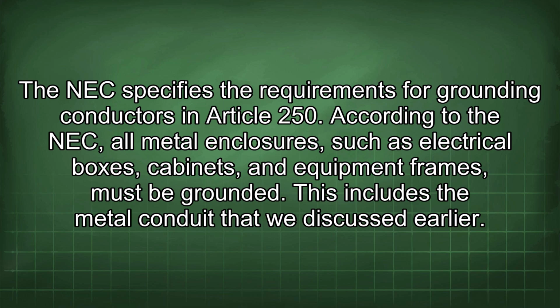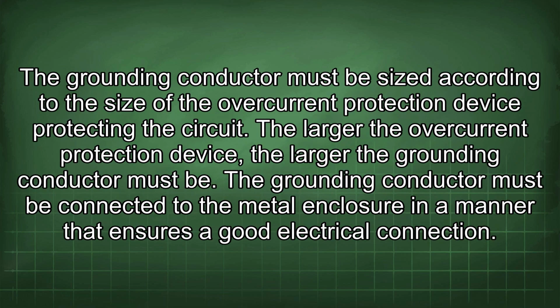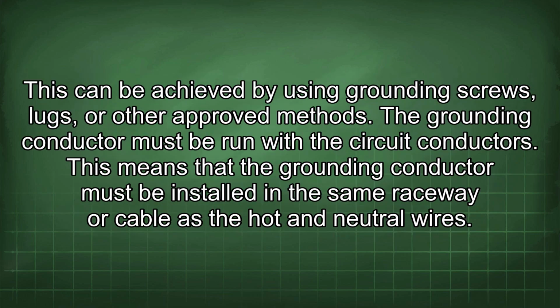According to the NEC, all metal enclosures, such as electrical boxes, cabinets, and equipment frames, must be grounded. This includes the metal conduit that we discussed earlier. The grounding conductor must be sized according to the size of the overcurrent protection device protecting the circuit. The larger the overcurrent protection device, the larger the grounding conductor must be. The grounding conductor must be connected to the metal enclosure in a manner that ensures a good electrical connection. This can be achieved by using grounding screws, lugs, or other approved methods.